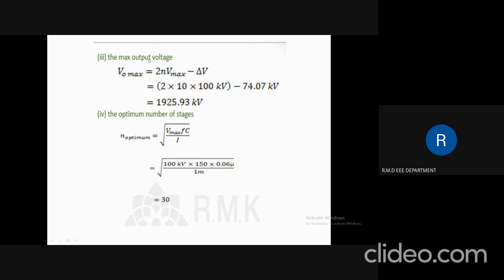The maximum output voltage is given by V₀_max = 2N·Vmax − delta V. Substituting N = 10, Vmax = 100 kV, and delta V = 74.07 kV, we get V₀_max = 1925.93 kV. To find the optimum number of stages, using N_opt = √(Vmax × FC / I), substituting Vmax = 100 kV, F = 150, C = 0.06 µF, and I = 1 mA, the optimum number of stages is 30.